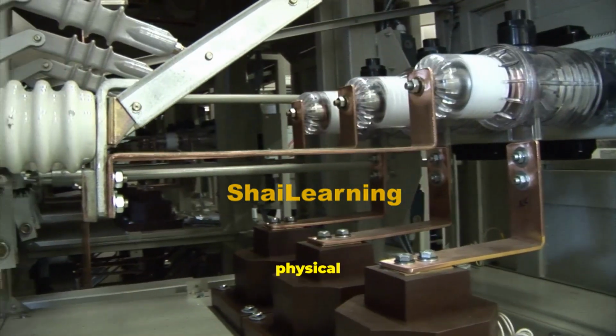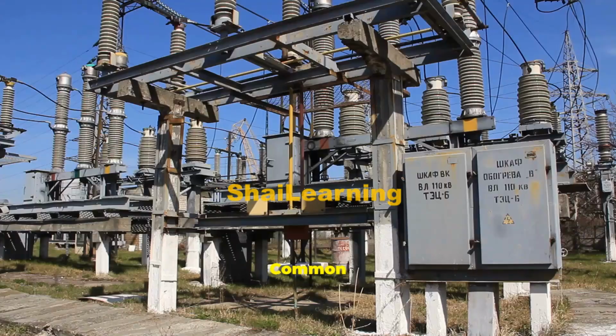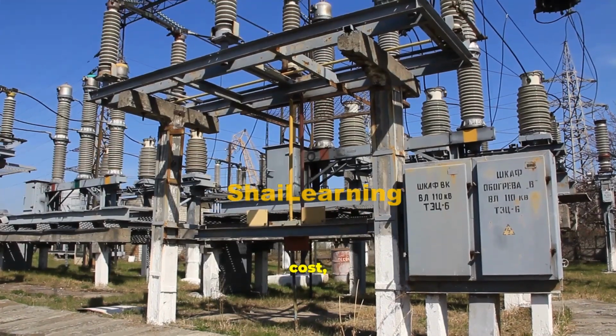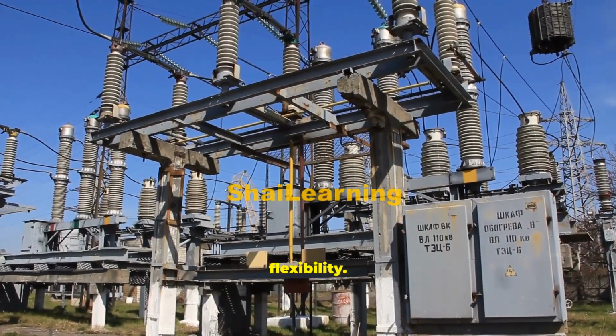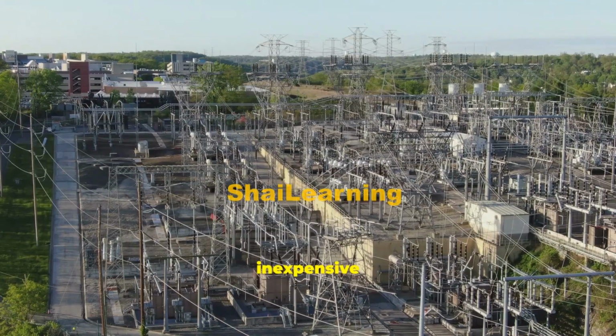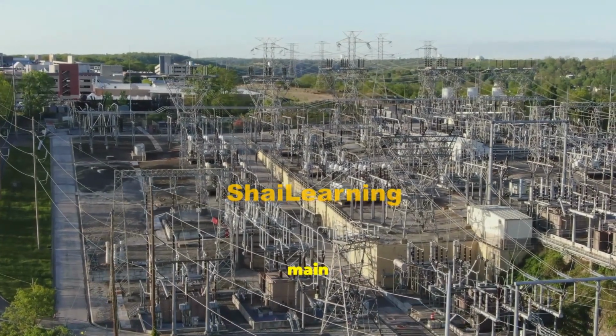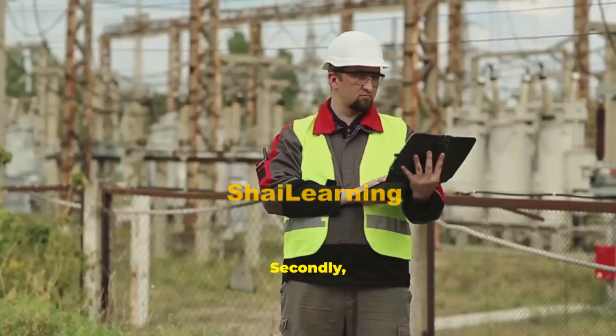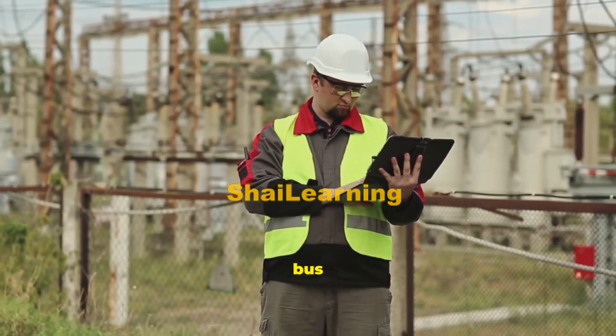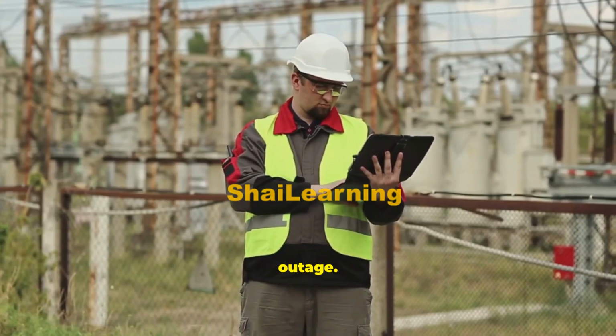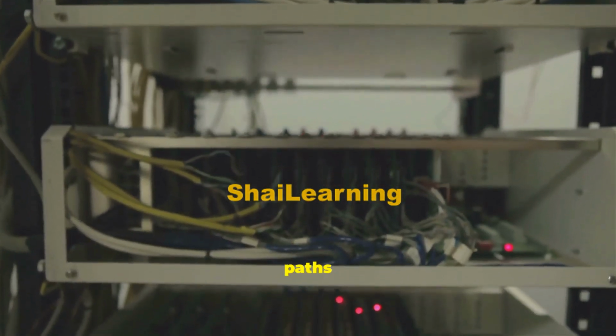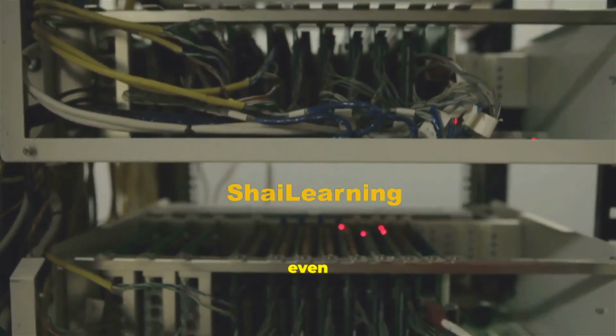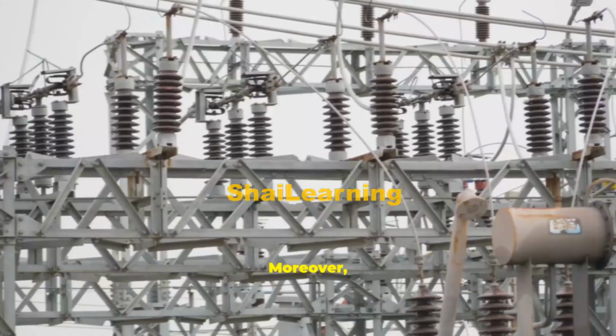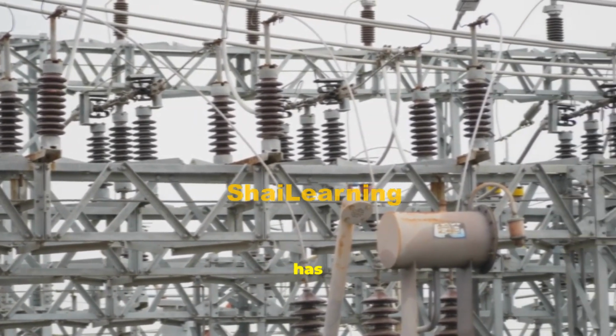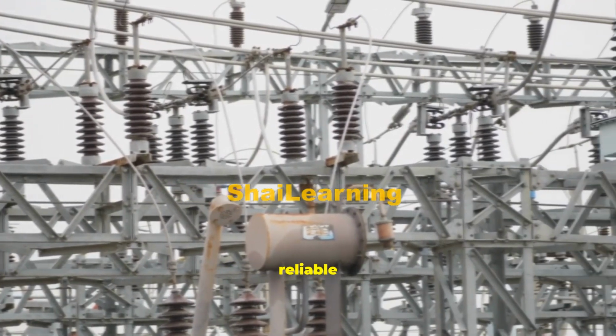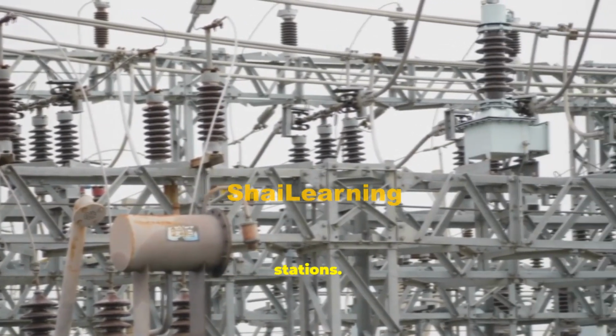Beyond the SLD, the physical layout on the ground is critical. Common substation configurations balance cost, reliability, and operational flexibility. Firstly, single bus. This is inexpensive but less reliable. A problem on the main bus can shut down the entire station. Secondly, main and transfer bus adds a backup bus to allow maintenance without a full outage. Thirdly, we have the ring bus. 2 paths to every circuit, so operation continues even if one breaker is out of service. Moreover, the breaker and a half scheme. This has 3 breakers for 2 circuits, highly reliable and flexible for critical high-voltage stations.